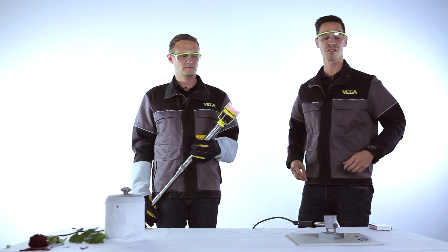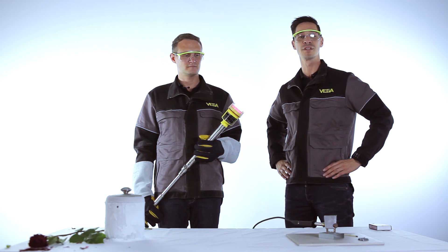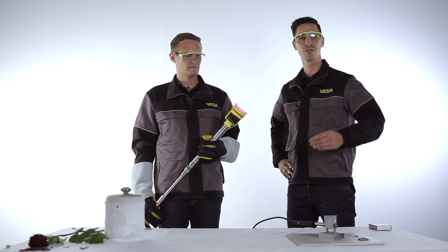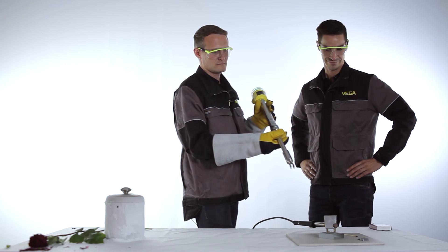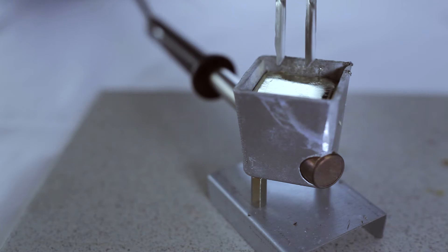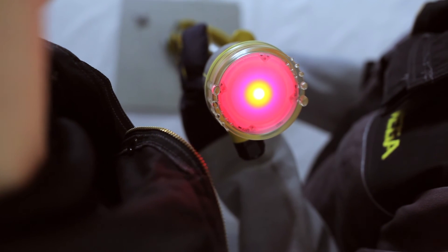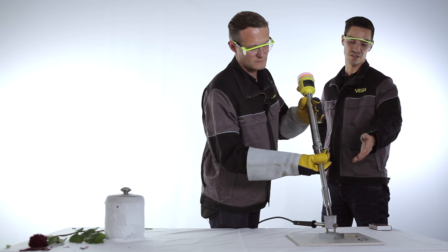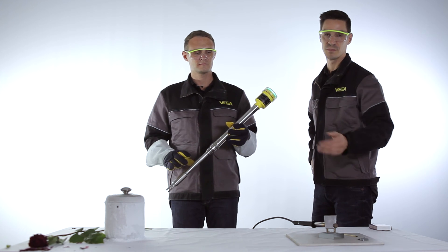The Vega Swing 66 is designed to survive temperatures up to 450 degrees Celsius. Now we put the fork into the liquid solder to see if it works. And now you can see the switching status has changed — even under these really hot conditions we have a reliable detection of the medium.